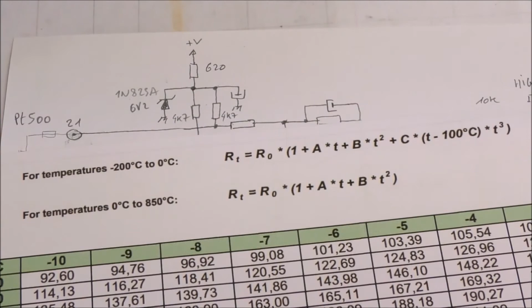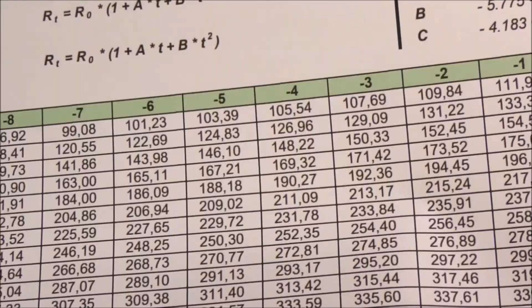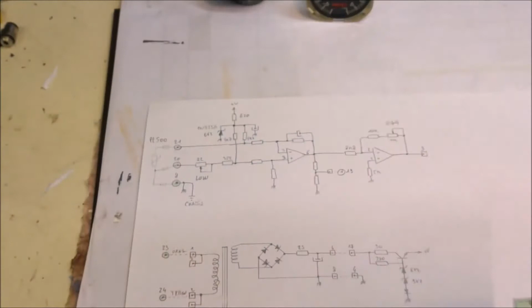If we take a look at the table of the platinum sensor of 500 ohms, we can see that for a temperature of minus 70 degrees, which is the minimum scale of this instrument, the resistance is 361.62 ohms. We can see that this is exactly the value of this resistor plus the mid-scale of this trimmer. So effectively this is a low adjustment.